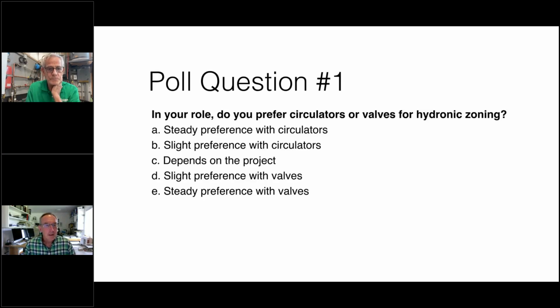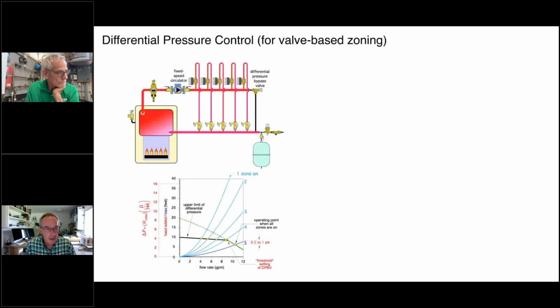Okay. Differential pressure control. As I mentioned, if we take this system, we've got 5 zone valves up here and a fixed speed pump. This was very common before ECM circulators. Most of the circulators driving flow in a hydronic system were fixed speed. They might have had speed settings, but at any given setting, the circulator just remains at a fixed speed. So if we look down here, when all the zones are open, we have our shallowest head loss curve, and where that curve intersects this green pump curve, that's our operating point.